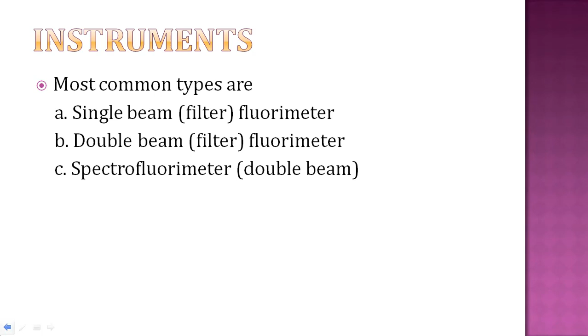Here the basic components of a single beam filter fluorimeter you can see. It is an inexpensive instrument, containing a tungsten lamp as a radiation source and an optical system composed of a primary filter and a secondary filter. The primary filter absorbs visible radiation and transmits UV radiation, and this UV radiation passes through the sample cell and gives fluorescent radiation which is in the range of visible radiation. So the secondary filter absorbs UV radiation if any is coming, and only transmits visible radiation because we want to transmit only the radiation emitted by the sample cell, and then this emitted radiation goes to the photomultiplier tube, meaning the detector, for detection.